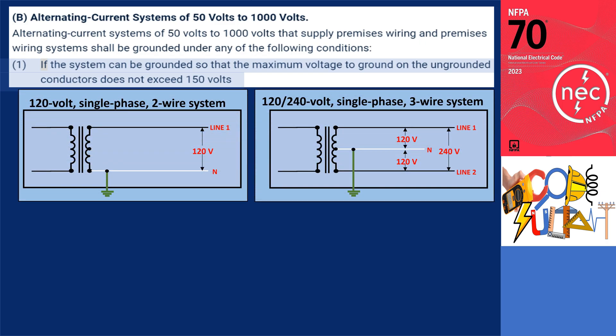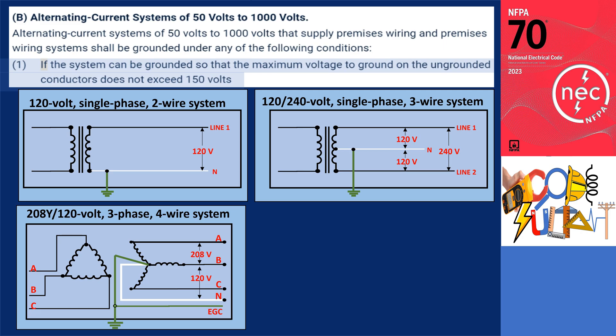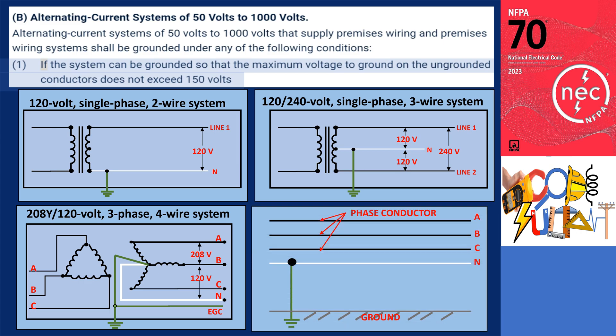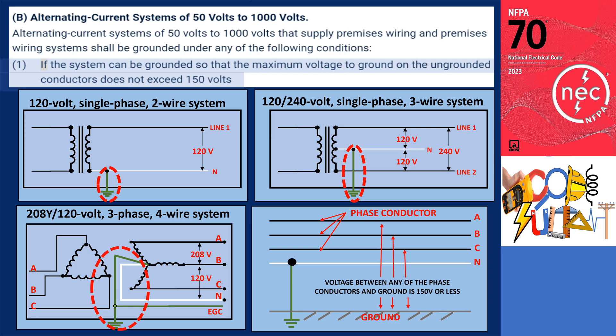The accompanying illustration demonstrates the grounding requirements outlined in section 250.20B1 for different system configurations. Specifically, it depicts the grounding requirements for a 120-volt, single-phase, two-wire system and a 120/240-volt, single-phase, three-wire system. Additionally, it showcases the grounding requirements for a 208Y/120-volt, three-phase, four-wire system. In all of these shown systems, it is necessary to ground the neutral conductor, because when the neutral conductor is grounded, the maximum voltage to ground does not exceed 150 volts from any other conductor within the system.